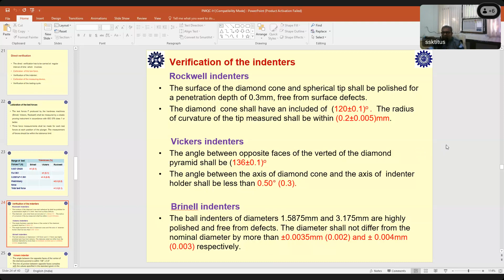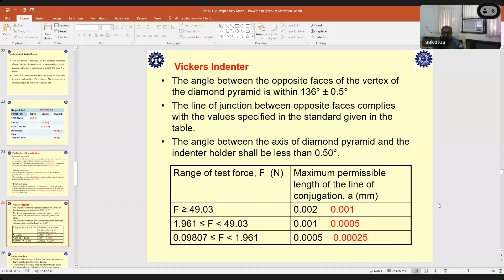Otherwise, the rest of the things are very simple. The only thing is you have to strictly follow the procedure given in the standard. For the hardness standard, again the indenter part is there, and for every range, the force. We already saw that it starts from 1 kg to 100 kg, and below 1 kg, 0.01 gram is also there, so that covers the entire range. What is the tolerance in the force? That is given here in this table, and you can see it. One is for the testing machine, the other one is for the calibration machine. The calibration machine always has to fulfill a little more stringent requirement.